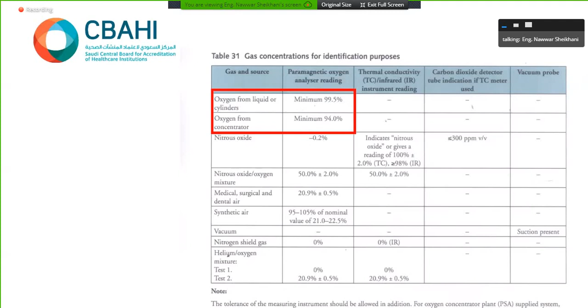Even for the concentration, the HTM gives us a reference to test the concentration of oxygen. Sometimes we have a very long piping system, so that's why you should measure the concentration of oxygen. For instance, at the source it could be up to 99.5 at the cylinder or at the LOX tank, but at the outlet in the patient room it should not be less than 94. And the FDA, or the American standard or reference, may be 92 or 93. This was one reason that we have chosen HTM. It always gives us the stronger criteria.